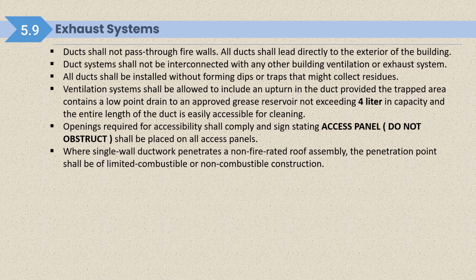Exhaust system. So exhaust system ducts shall not pass through firewalls. All ducts shall lead directly to the exterior of the building. Duct system shall not be interconnected with any other building ventilation or exhaust system. So kitchen hood exhaust should not get connected with any other building ventilation or exhaust system.